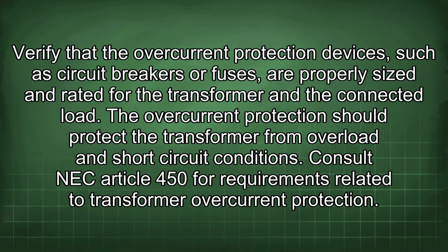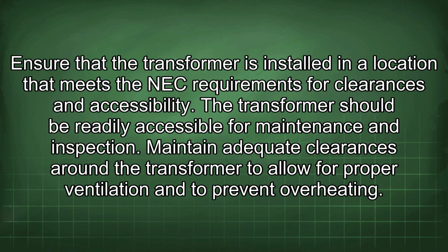Verify that the overcurrent protection devices, such as circuit breakers or fuses, are properly sized and rated for the transformer and the connected load. The overcurrent protection should protect the transformer from overload and short-circuit conditions. Consult NEC Article 450 for requirements related to transformer overcurrent protection. Ensure that the transformer is installed in a location that meets the NEC requirements for clearances and accessibility. The transformer should be readily accessible for maintenance and inspection.